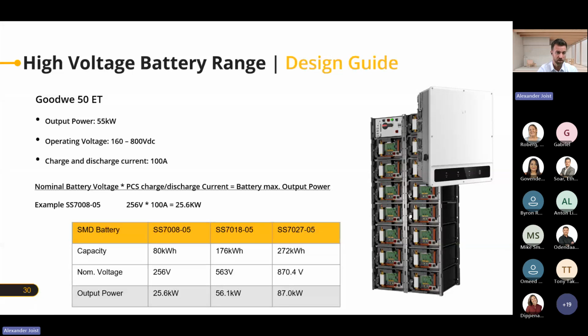For this inverter, unfortunately, with the 50 kilowatt inverter, the 100 amps is a bit low, but at the same time, you can use the ET25, right? If you use the ET25, which also has 100 amps, you can use the 80 kilowatt hour battery and have 25 kilowatt output. There it fits actually. There it's not too bad. You don't have to have too big of a battery. So even the ET30 will work. ET30 also has 100 amps. So always calculate your output power on the batteries and your inverter.